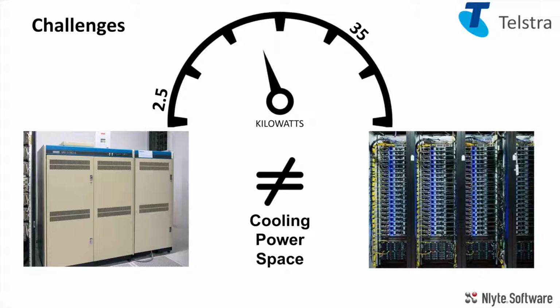I think one of the biggest challenges in our environment is just the speed of growth that we've seen in the last 20 years. Prior to that, if you pulled 300 watts a cabinet or a kilowatt a cabinet, that was a really high density deployment. If you built or refreshed facilities 15 or 20 years ago, and you built for 2.5 kilowatts per cabinet, that was a really high powered floor. And 5 years later, when you're building them, that's not going to do the job for you.